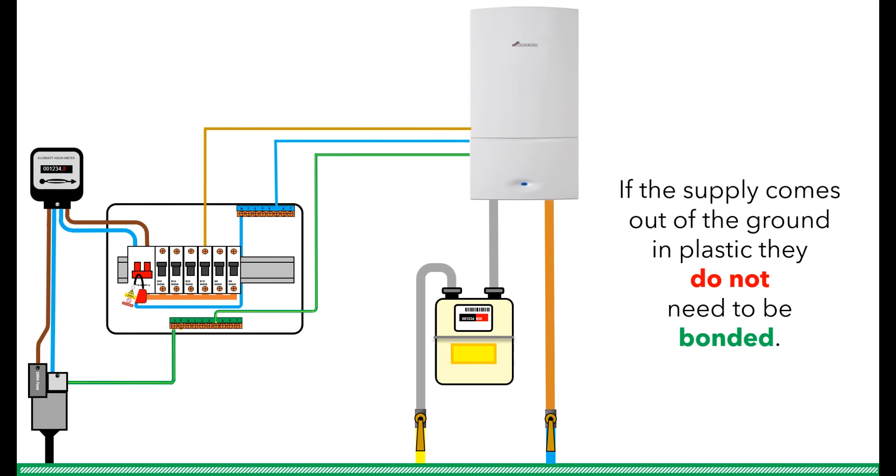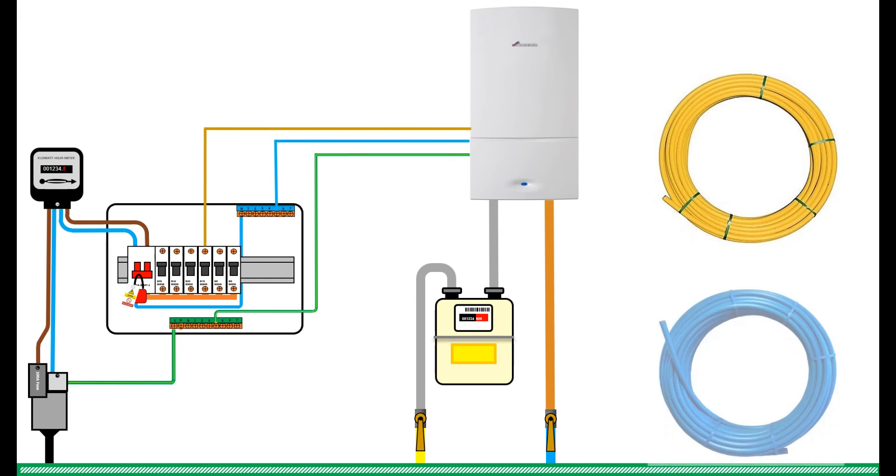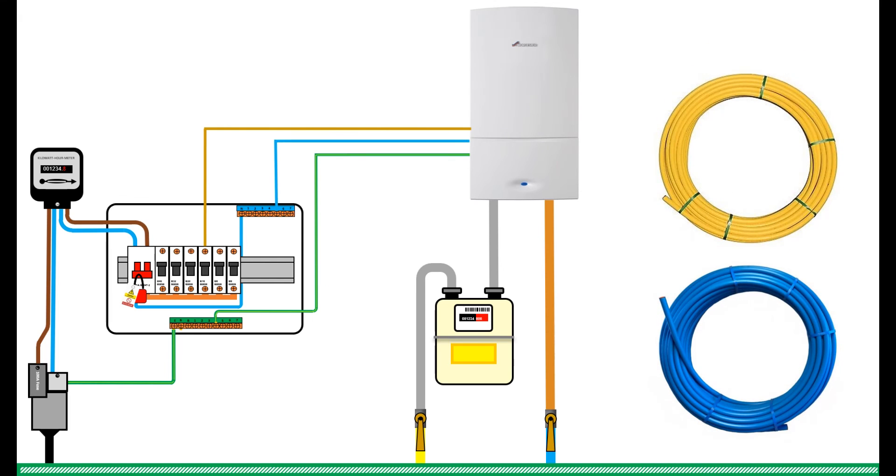If the supplies are coming out of the ground in plastic, which most new supplies are, then they do not need bonding. The gas will be yellow MDPE pipe, and the water will be blue. And being plastic, they are non-conductive.